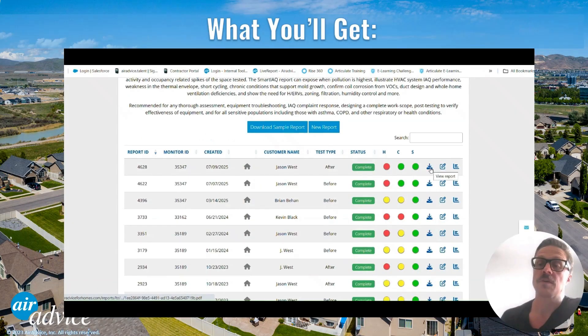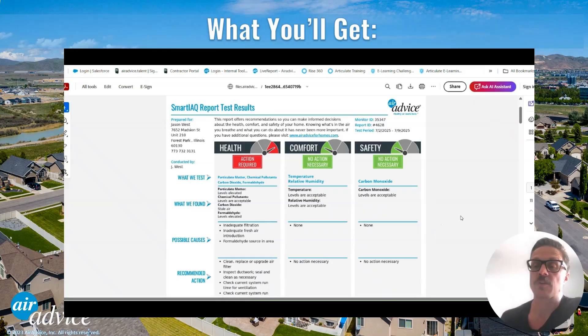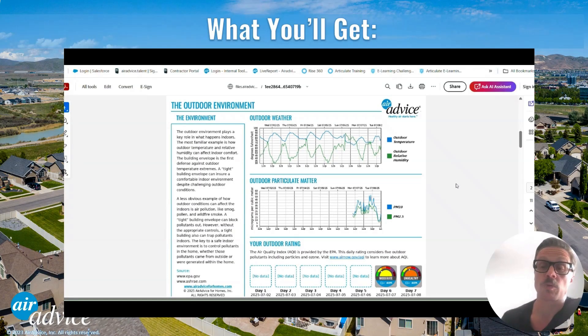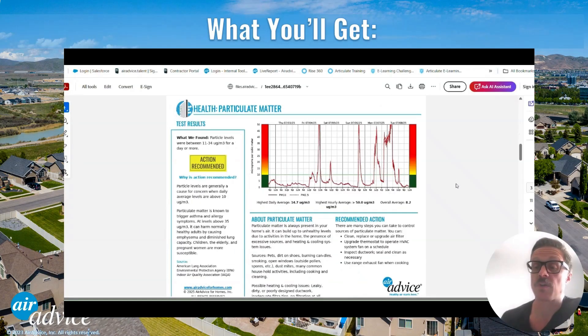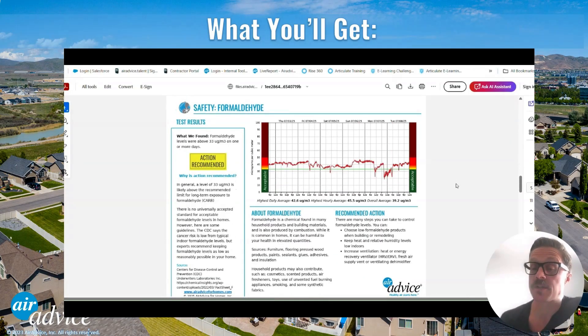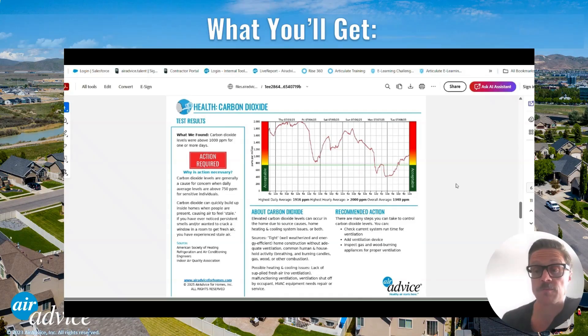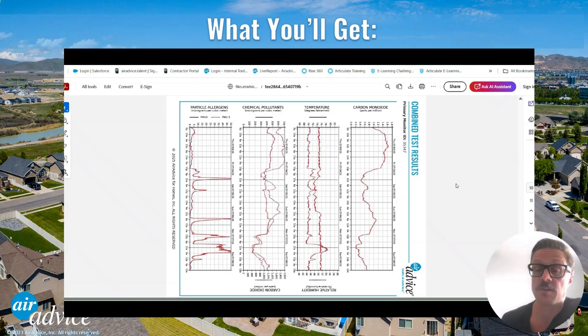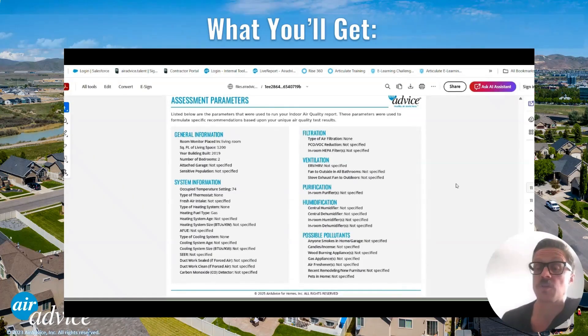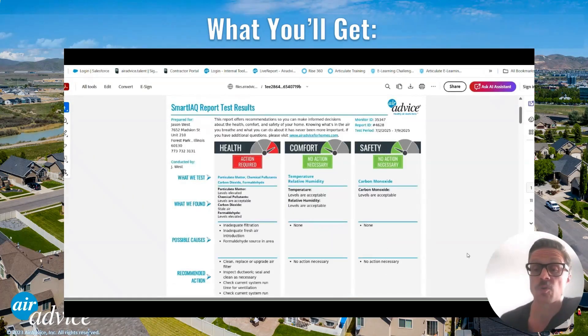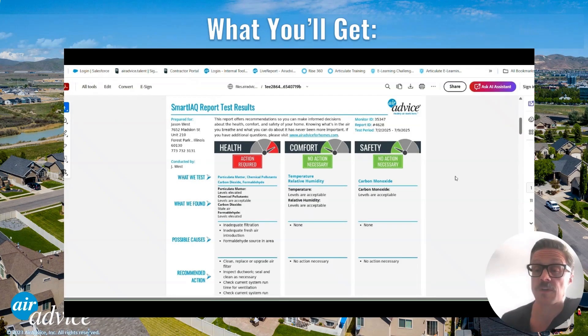And this is what you'll get. Download the finished PDF from the list. Look for that little download icon, and you'll get a Smart IAQ report. It breaks down health, particles, chemicals, carbon dioxide, comfort — which is temperature and relative humidity — and safety, which is carbon monoxide. You'll see the action levels: green is good, yellow means watch out, red means it's time to get it fixed. And there are easy graphs that show IAQ events when they happen.